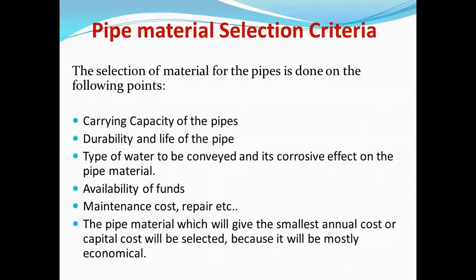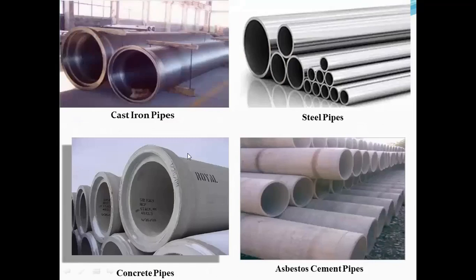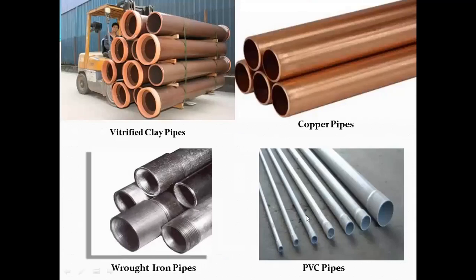Next point is availability of funds. If funds availability is less, we should prefer a less costly pipe system. If funds are more, we can go for costlier pipes. Then maintenance cost and repair: the pipe should be selected such that it has less maintenance and less repair work. Cast iron, steel, or wrought iron pipes can corrode and need to be replaced. Concrete, asbestos, or PVC pipes have lower maintenance, though PVC pipes may have leakage at joints.